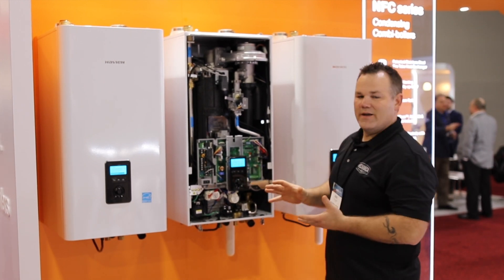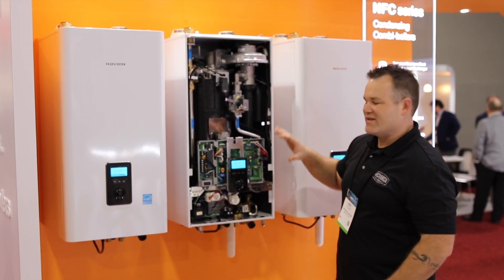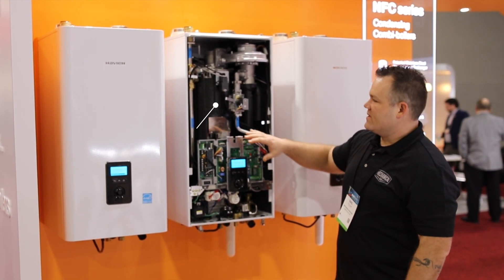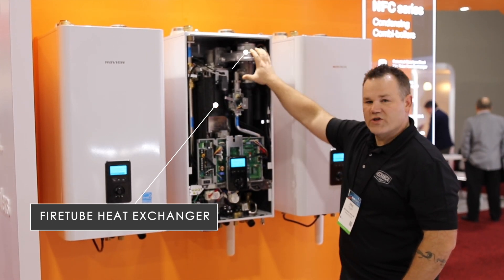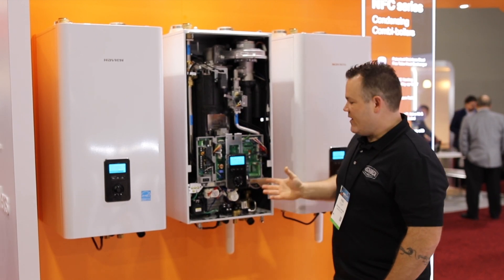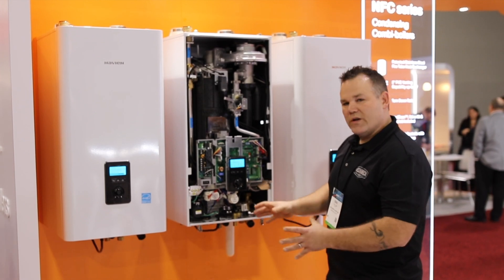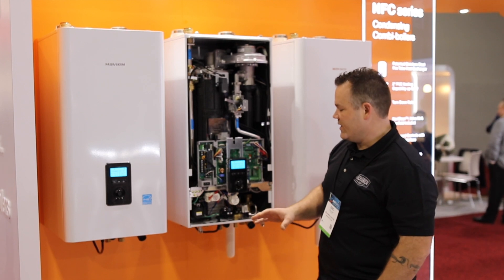I'm at the Navien booth at AHR Expo. This is a brand new product from Navien — I have not installed it yet but I'm super intrigued to see what it's all about. I want to show you a couple things on this new combi boiler, the NFC. It's a fire tube heat exchanger made by Navien with a negative pressure gas system and an 11 to 1 turn down ratio. What's significant is that they've combined this to make it a combi boiler for domestic hot water production — totally new and innovative design on the market.